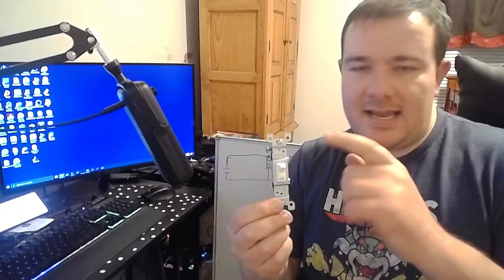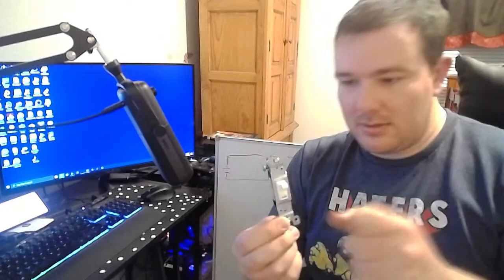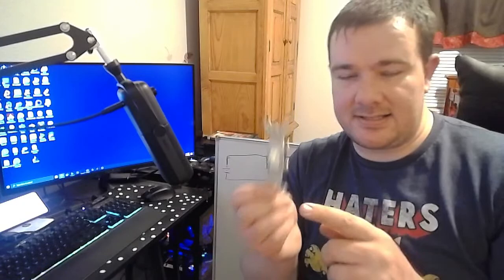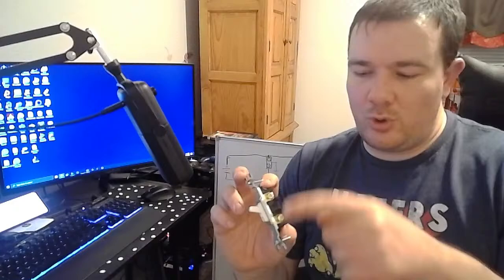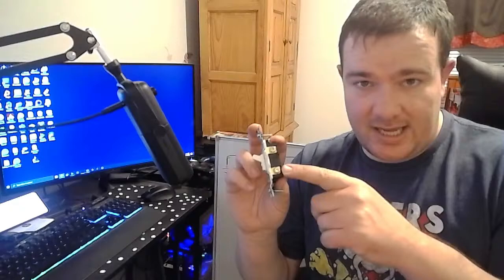Now, some switches have little LEDs in them, and they will have an extra screw that is your neutral. But this one does not because it does not have any lights in it. This is a bare bones electrical switch. So you have two hot wires. One is your line in or your feed, and the other one is referred to as the switch leg. The switch leg is the leg on the switch, hence the name, that goes to your device.